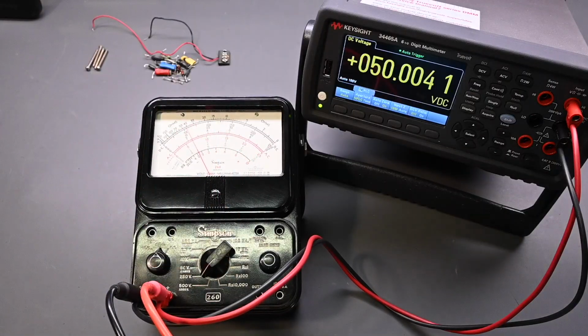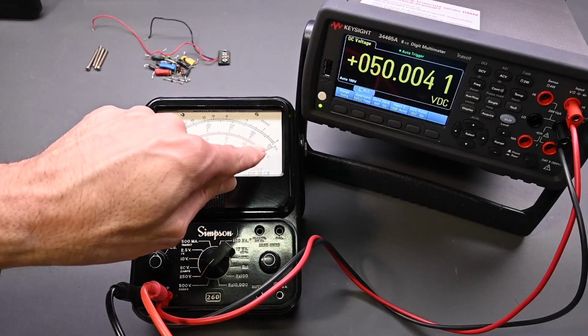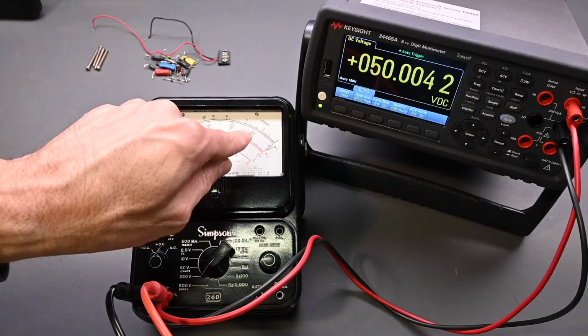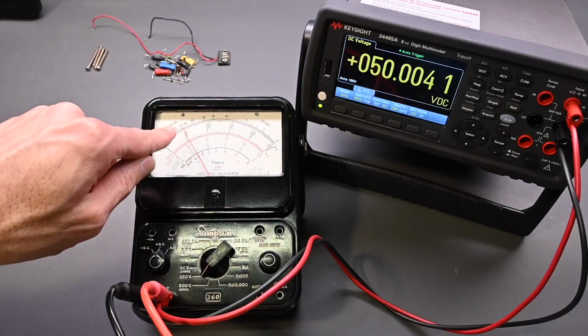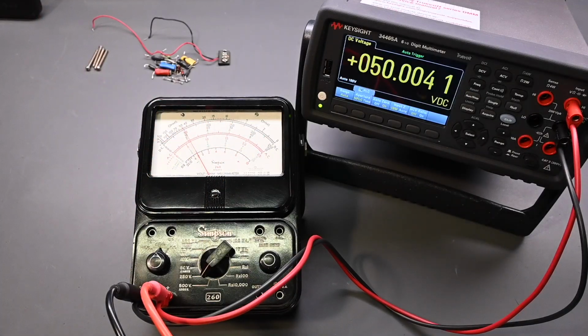I'll go to 250 volts. So on 250, you're reading on this top scale, so you have 250, 200, 150, 100, and then 50, so that's exactly what it should be. And the Keithley 236 tops out at 110 volts, so I'll just go to 100 right there, and exactly where it should be, right on.